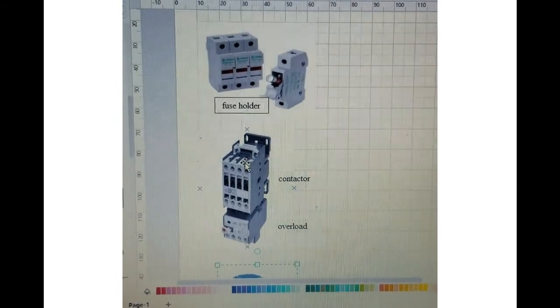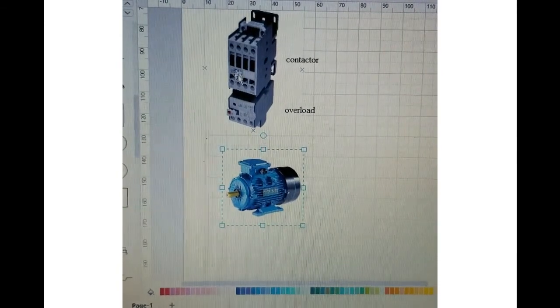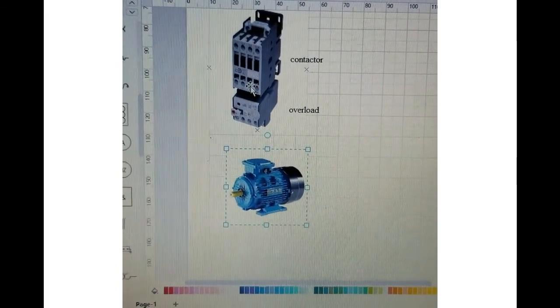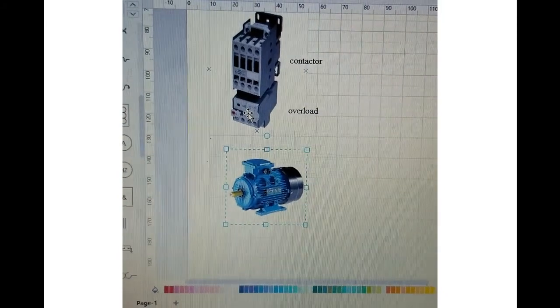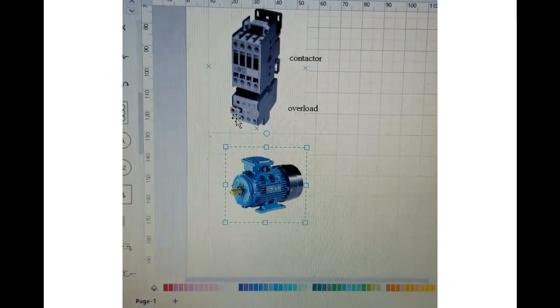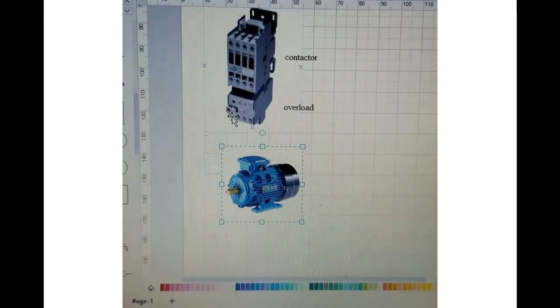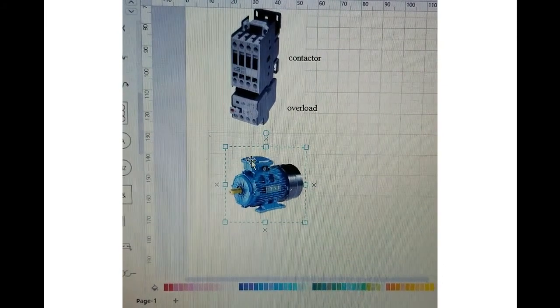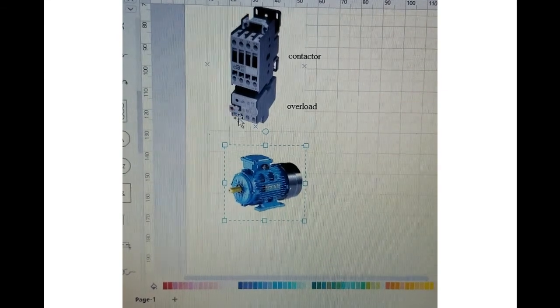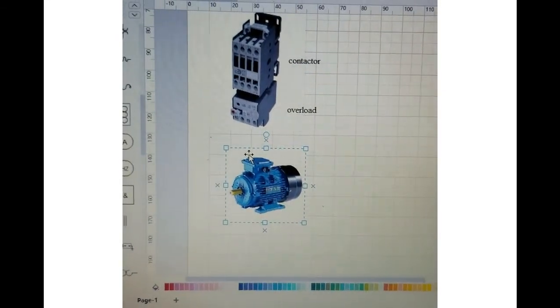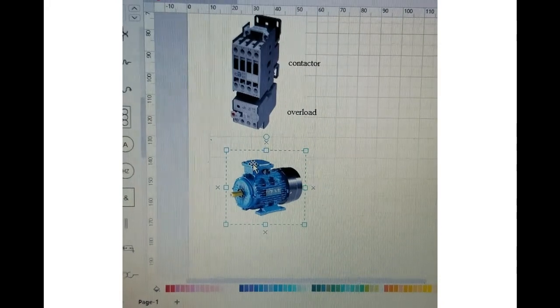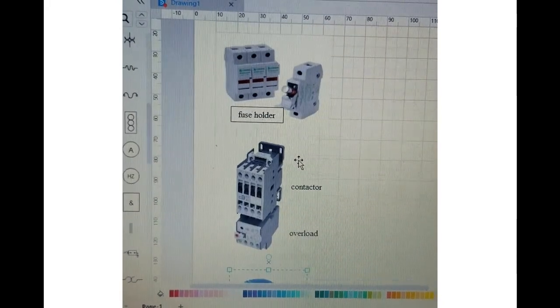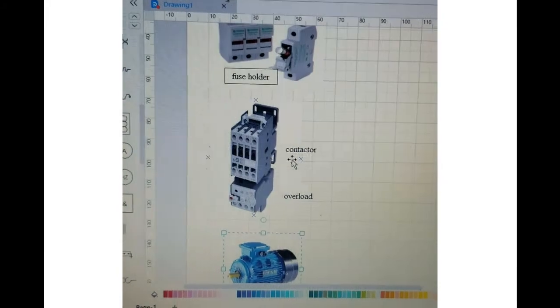Then that L1, L2, L3 will make a contact here and they will pass out through the overload. And yes, you can see from the overload terminals, the first terminal will go to one wire on the motor, L2 will go to the second wire on the motor, and L3 will go to the third wire on the motor.